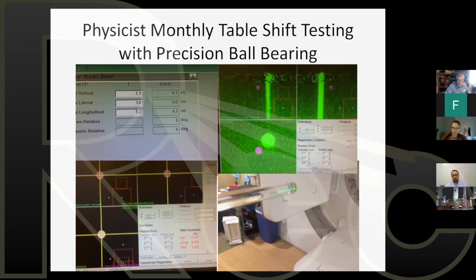Obviously, it's going to be off from the reference image. This is what it looks like here. It shows you that where the BB is not where the reference is. It's off because I deliberately put it off. I cone beam CT it with this offset. Then I use the software to correct it.